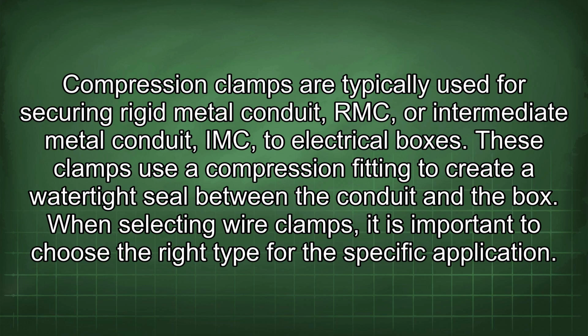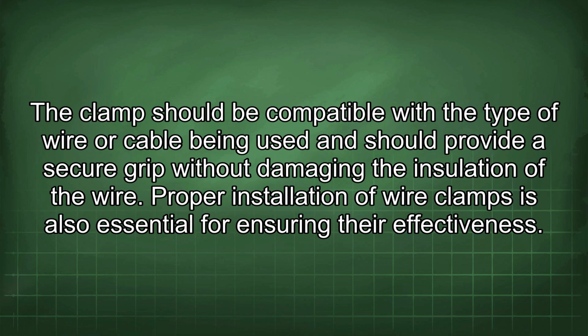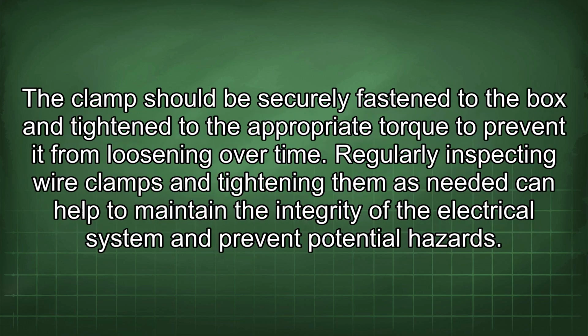When selecting wire clamps, it is important to choose the right type for the specific application. The clamp should be compatible with the type of wire or cable being used and should provide a secure grip without damaging the insulation of the wire. Proper installation of wire clamps is also essential for ensuring their effectiveness. The clamp should be securely fastened to the box and tightened to the appropriate torque to prevent it from loosening over time. Regularly inspecting wire clamps and tightening them as needed can help to maintain the integrity of the electrical system and prevent potential hazards.